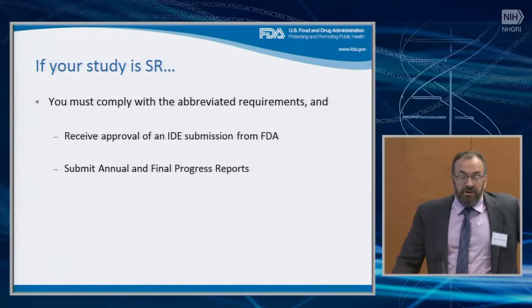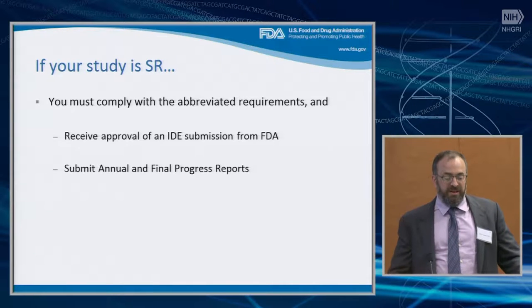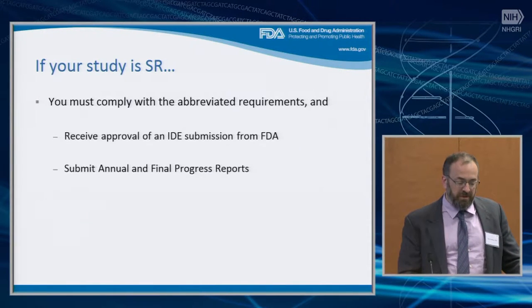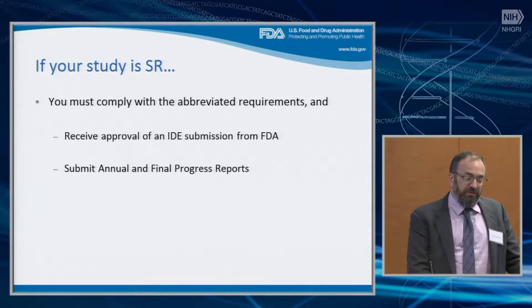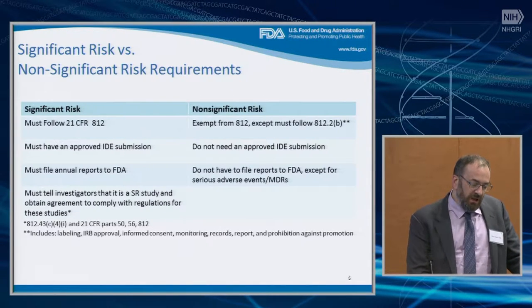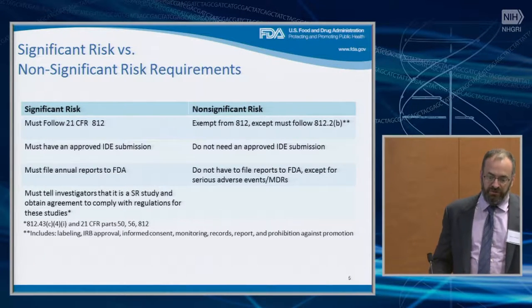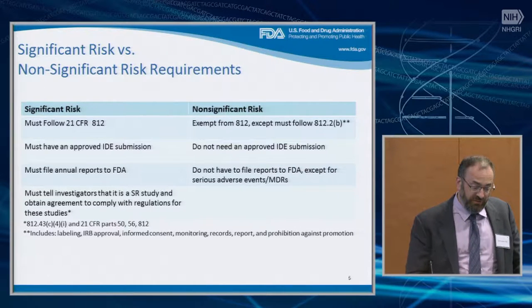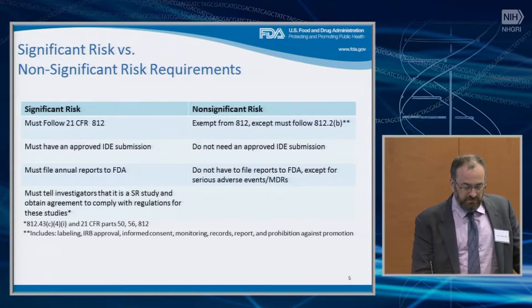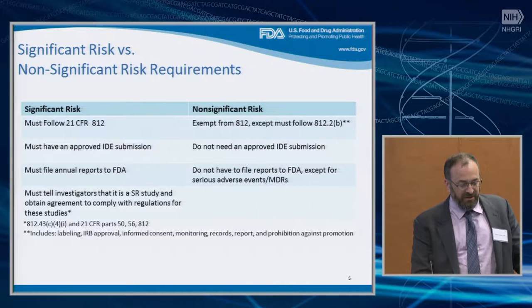Obviously, if you are significant risk, you have to receive an approval of an IDE submission on top of the other requirements, and you will have to do annual and final progress reports. This is just a handy table that compares the two categories. Investigator agreements as well — that has to be taken into account in a significant risk study.